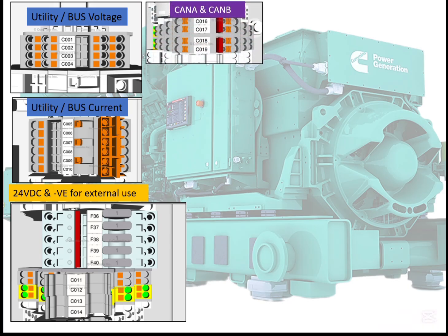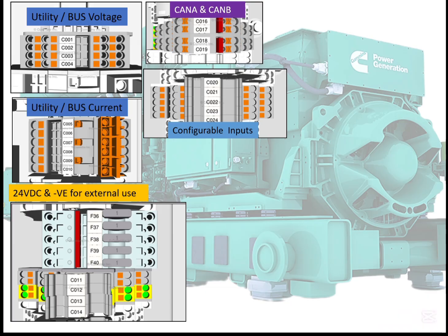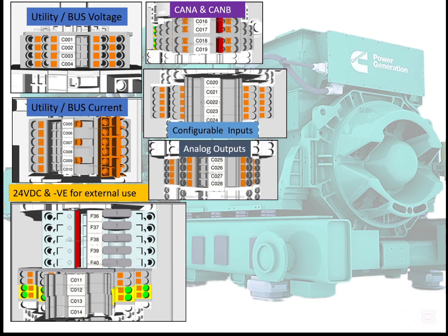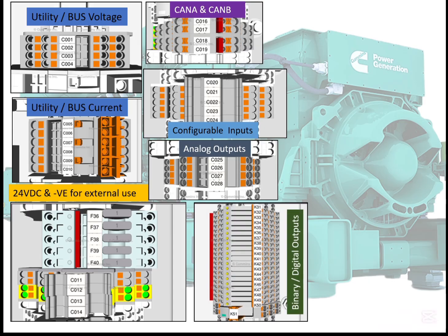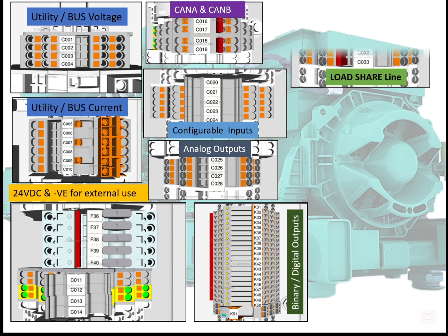This is the CAN bus, CAN A and CAN B. These are the configurable inputs that we mentioned, the analog inputs. These are the analog outputs, by kilowatt and others, all of them configurable too. These are the binary digital outputs, K31 to K50 and K51. K31 to K50 are data such as warning, shutdown, genset CB on and off, utility CB on and off, genset running. K51 is remote emergency stop.